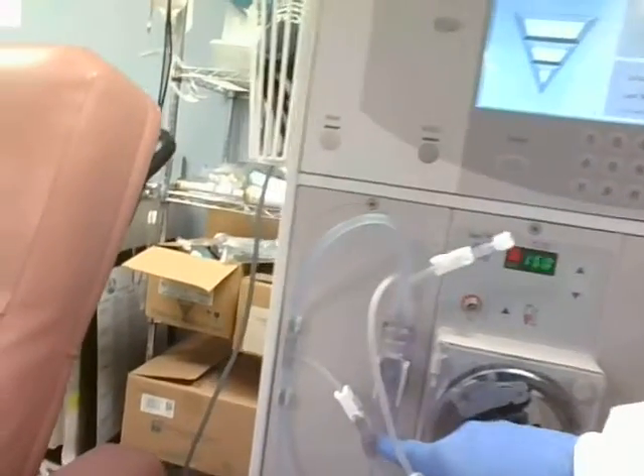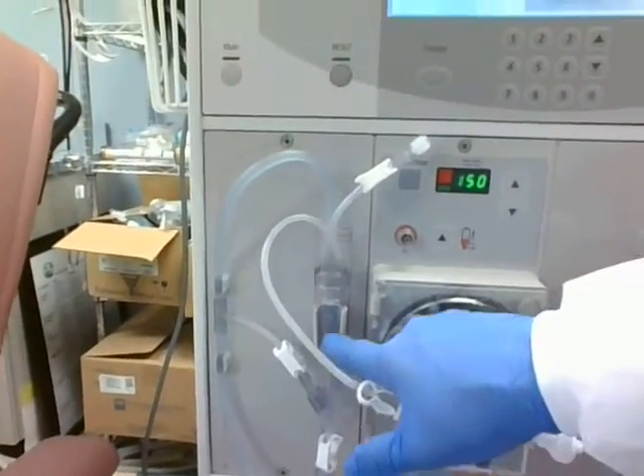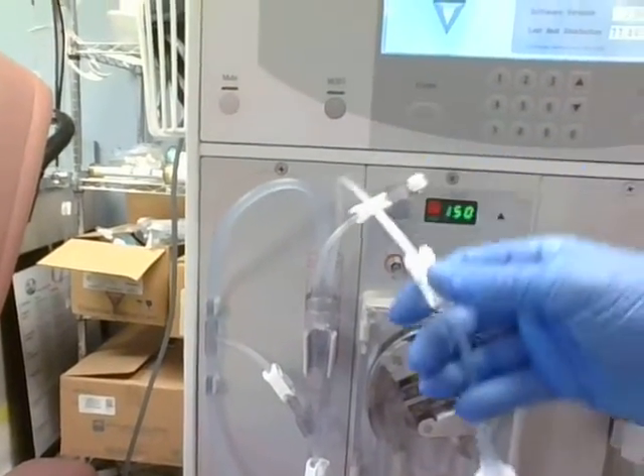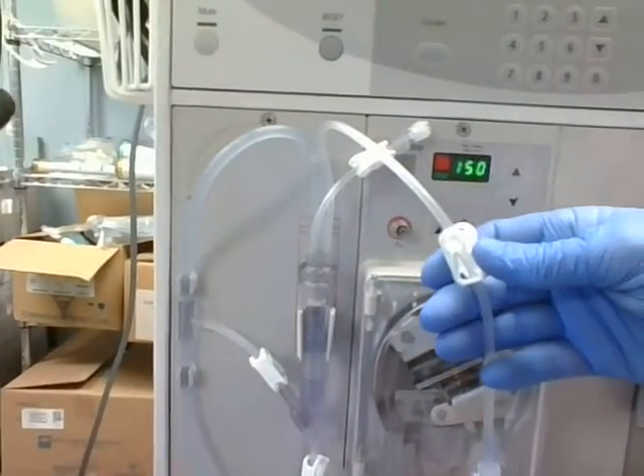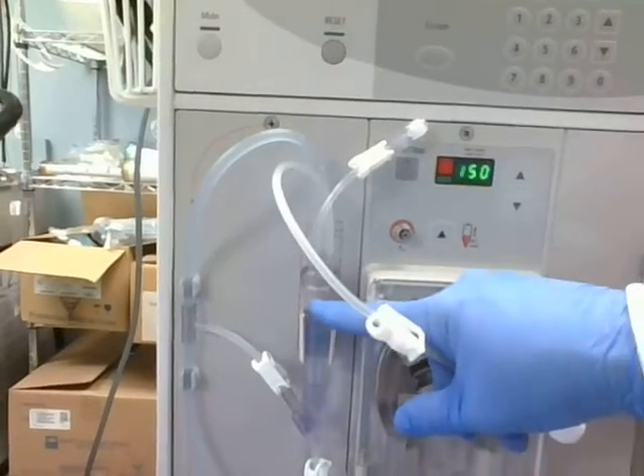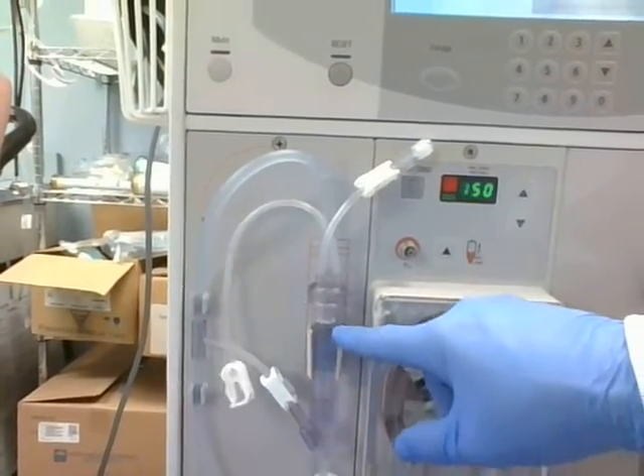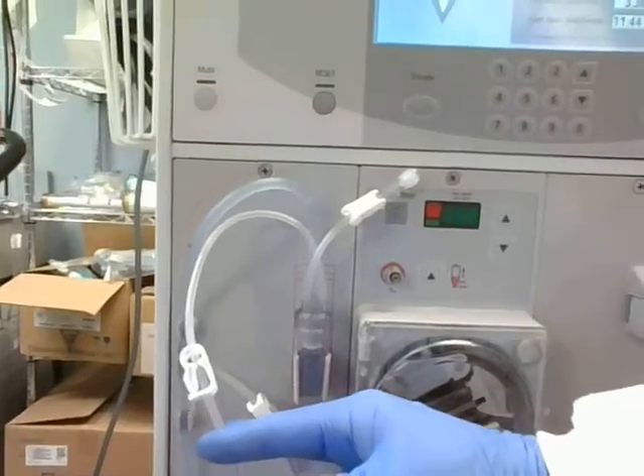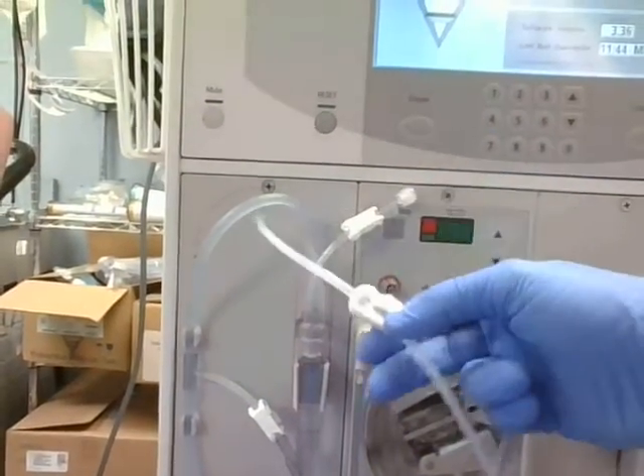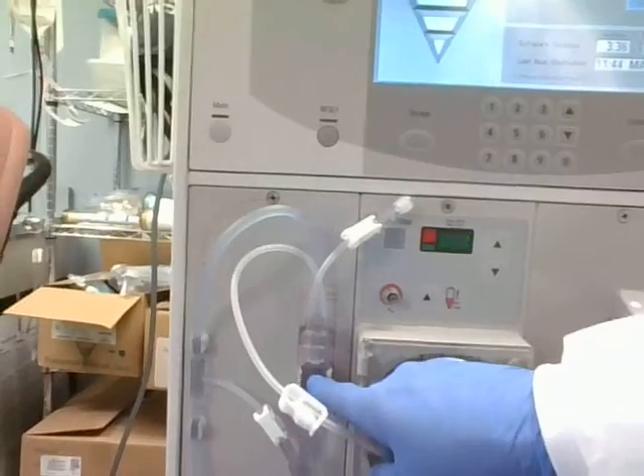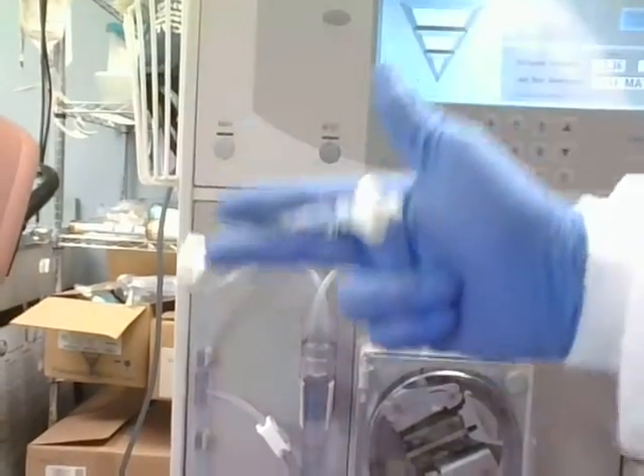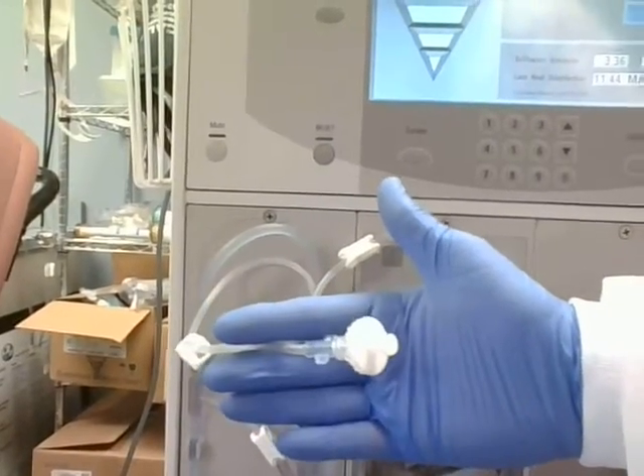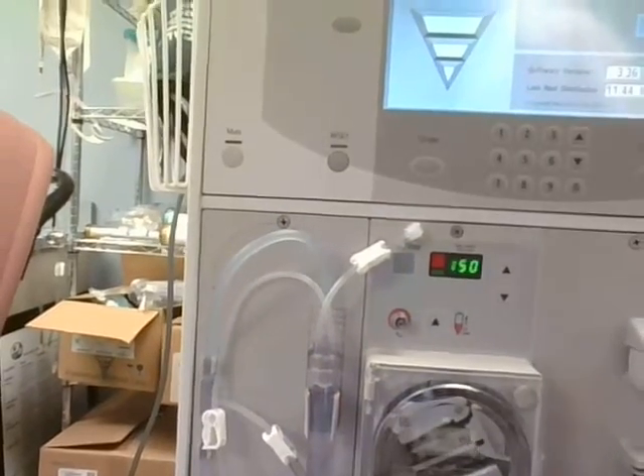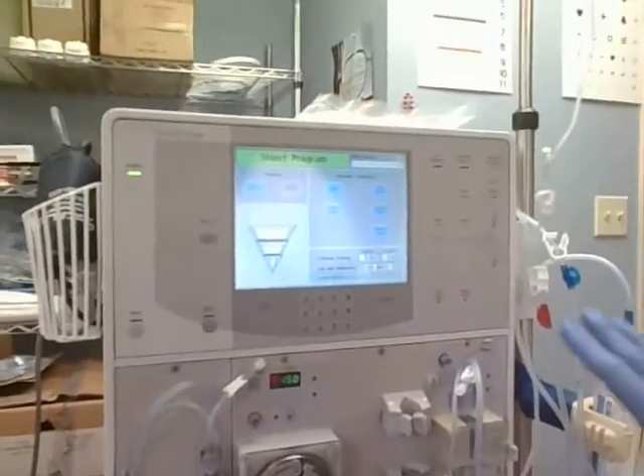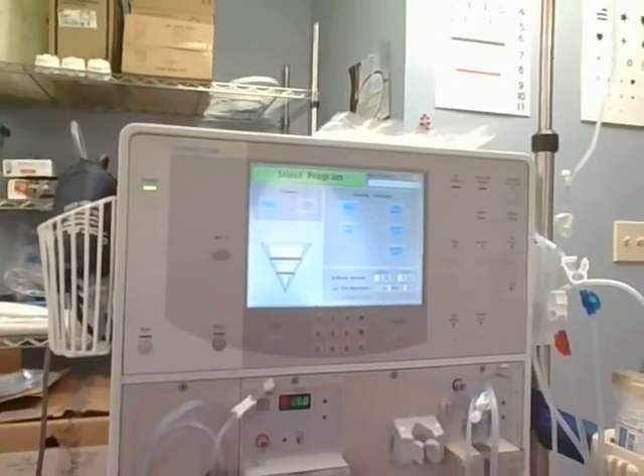So when I unclamp this, I want you to watch the saline level in my drip chamber. Unclamped, see that saline coming up? When it reaches the fill mark on your drip chamber, be sure you clamp that back and make sure you get your transducer protector line clamped before the fluid gets all the way up here and into. If you wet your transducer protector, you got to start all over. All right, at this point, this machine is ready for prime.